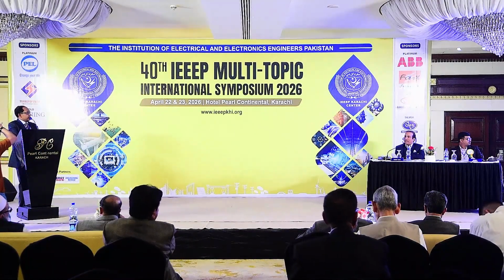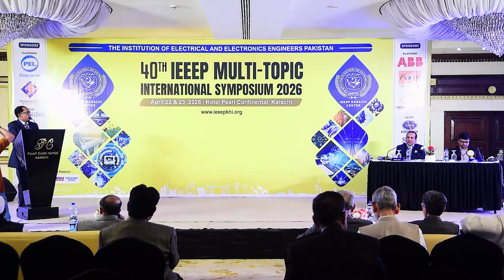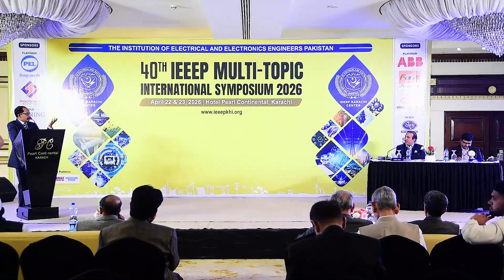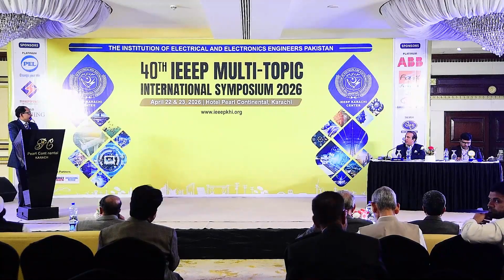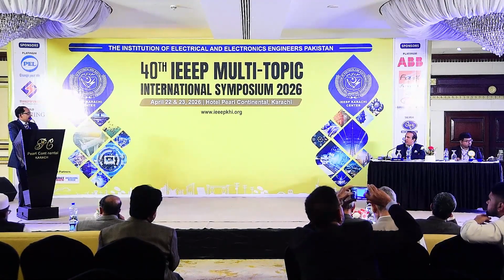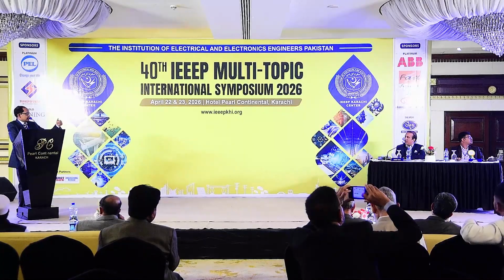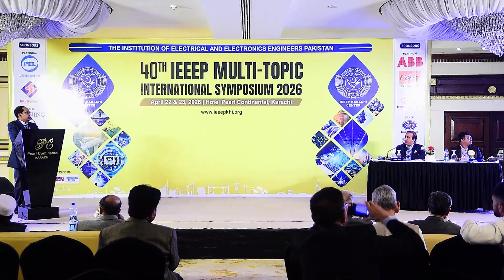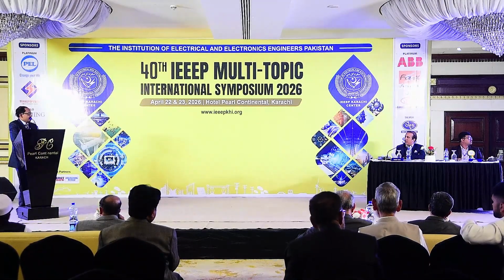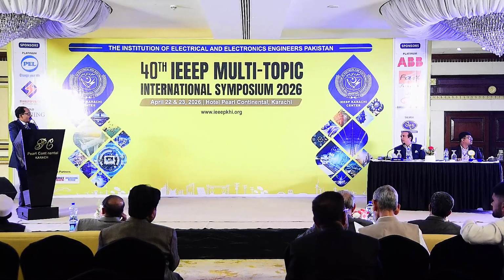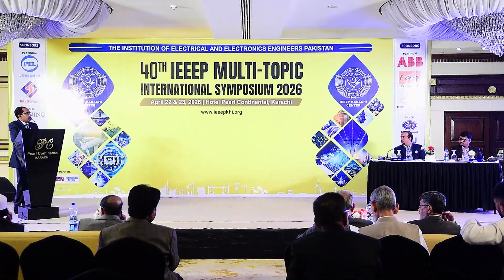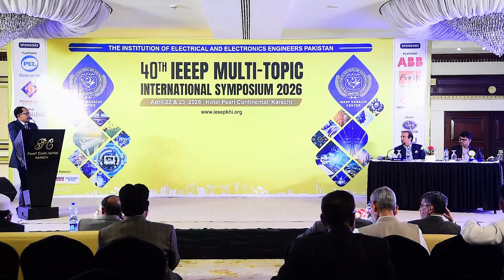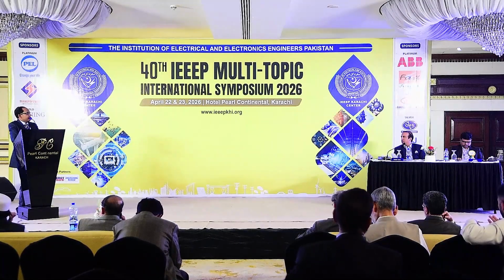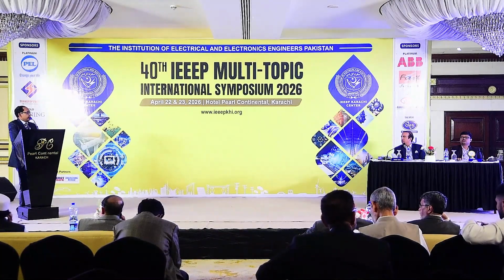So what happens now when there is the availability of a microgrid controller system? A similar fault occurs in the system, causing the grid to go on outage. Ultimately, the genset will also go on outage. The WTG will also go on outage, and the non-critical load will not be served immediately. The prime theme for industries is that during that period you have to provide a backup to critical loads, which run their processes of prime importance.